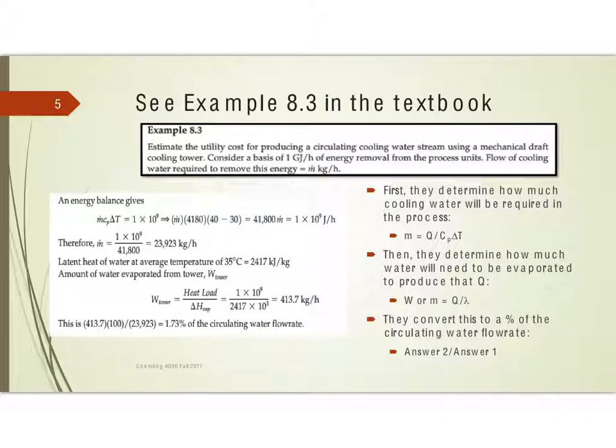So, the first thing they do is they figure out how much cooling water is going to be required. So, just doing a simple material balance, q equals mc sub p delta t, solve for the mass of the cooling water. Remember, our delta t is going to typically be going from 30 degrees to 40 degrees. So, 10 degrees is our usual design delta t.